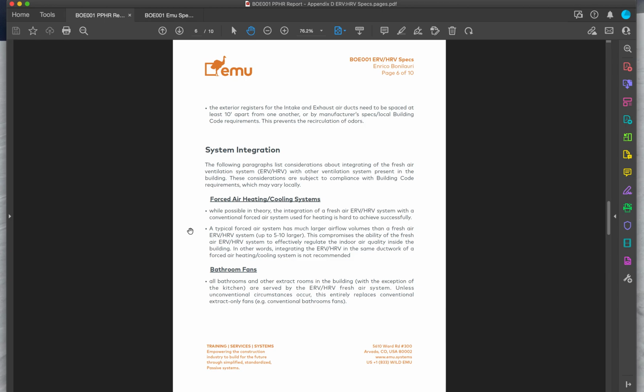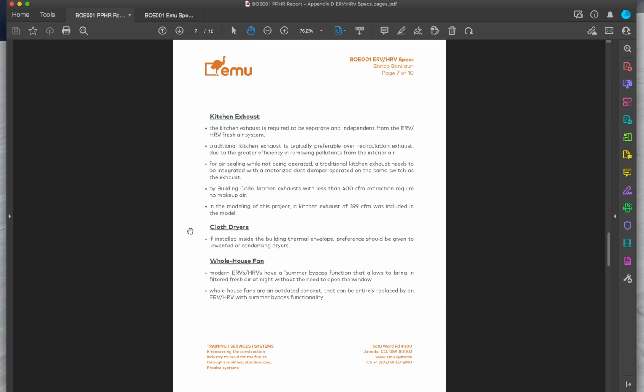and there goes your indoor quality out the window. Bathroom fans are going to be entirely hooked up into the ERV system. No actual fans, just the ERV venting those spaces. No need to use the conventional bathroom fans. Kitchen exhaust, we recommend to have a dedicated exhaust with a mechanical damper. Clothes dryers, we recommend using a ventless condensing dryer. Whole house fans are a thing of the past, hopefully, and modern ERVs and HRVs have a function called summer bypass that allows you to get the same function as the whole house fan, but no need to open the windows. You get free cooling at night with filtered fresh air.